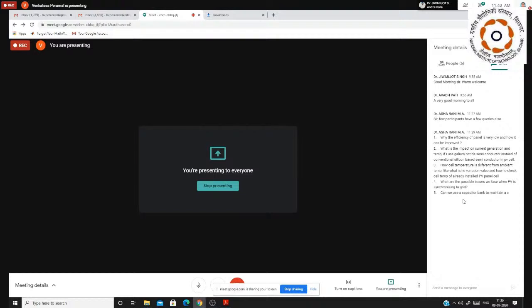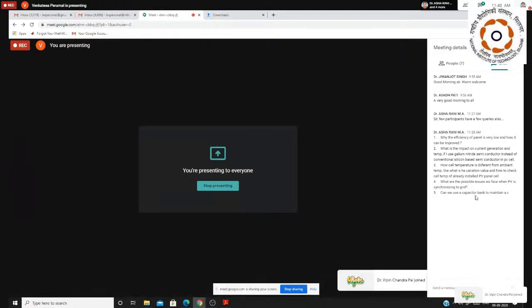So the first thing is grid synchronization. The PLL concept needs to be thoroughly understood before implementation. Because if you push power without synchronizing properly, in an unaligned way, angle changes will happen, there will be a phase difference, and frequency mismatches. Think of it this way, worst case, not something that would really happen: if your inverter frequency is 51 Hz and the grid frequency is 50 Hz, what will happen?